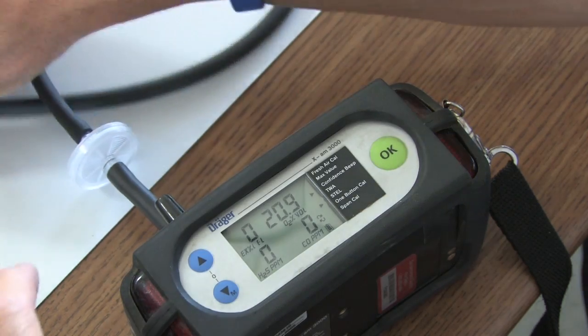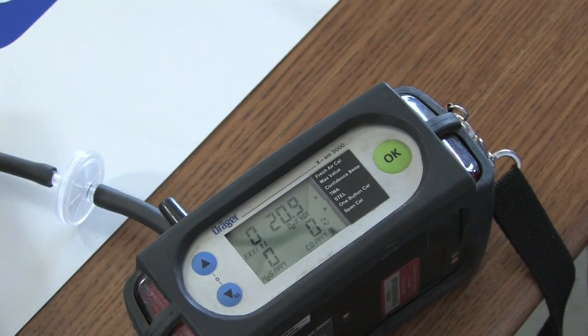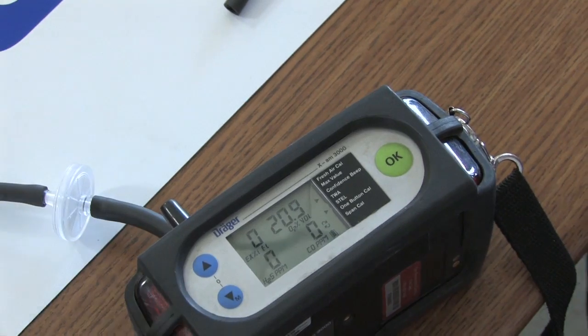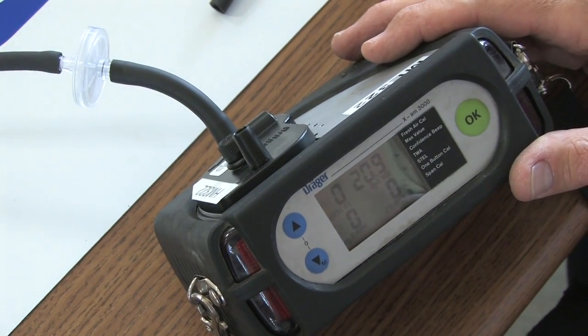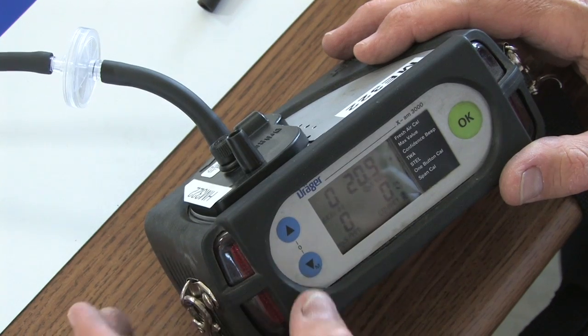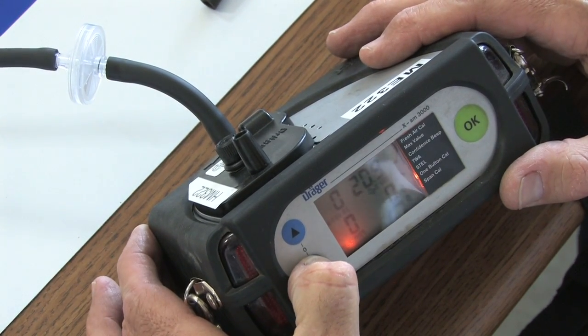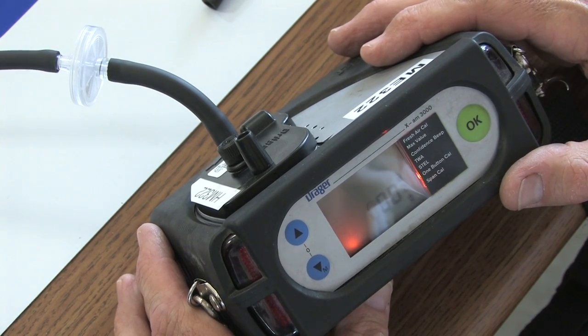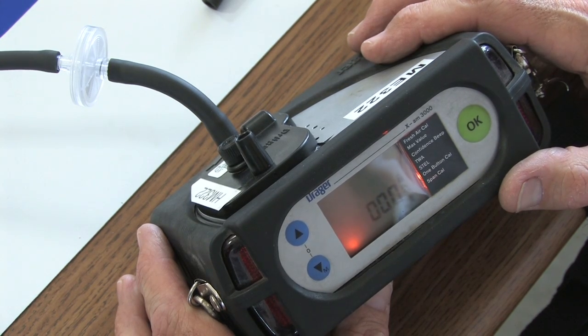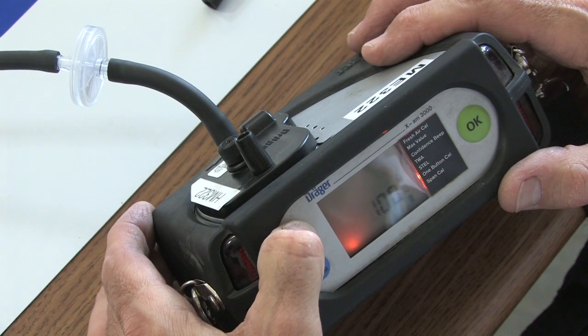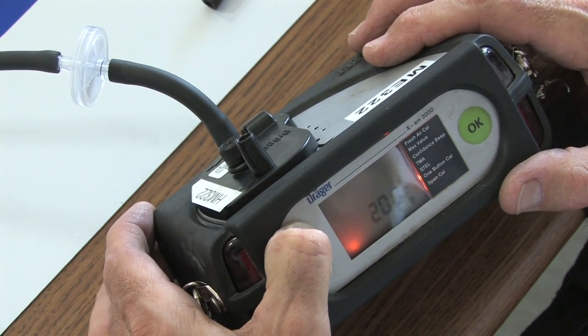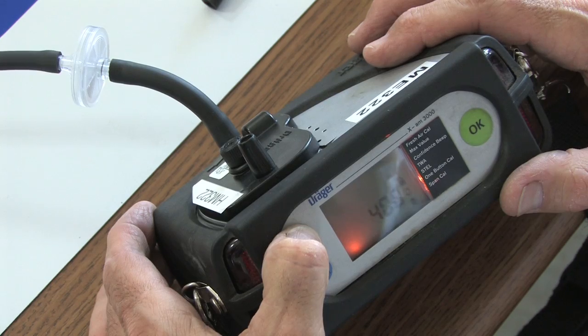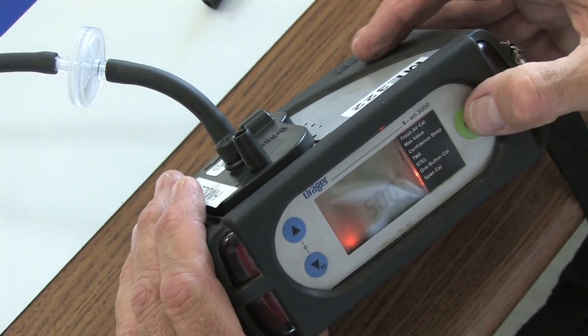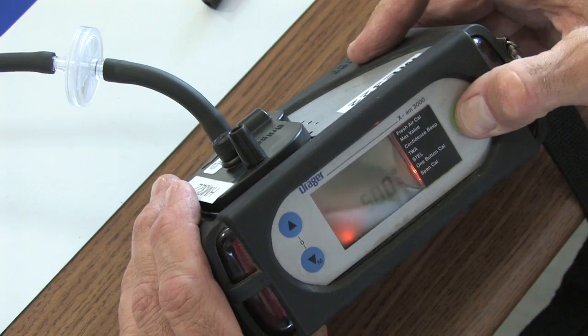And here's how you calibrate an X-am 3000. A little bit different than any other Draeger meter that I've ever seen. What I'm going to do is I'm going to take my down arrow and I'm going to hold it down all the way and keep holding it down. And then a password is prompted. Now the password on the X-am 3000 is 500. So I got to hit the up arrow to keep adding a number. And there's my 5. I hit OK to go to the second digit, OK to get to the third digit.